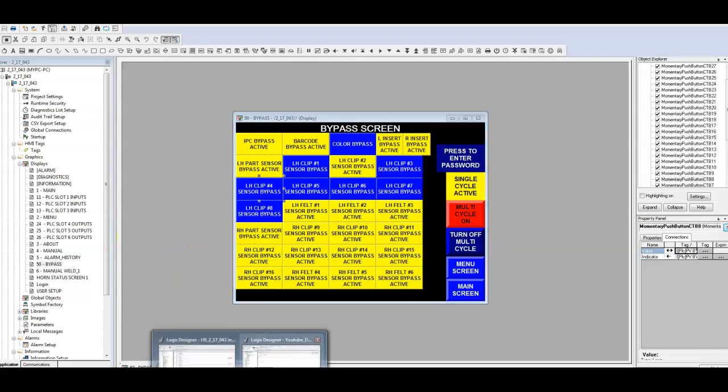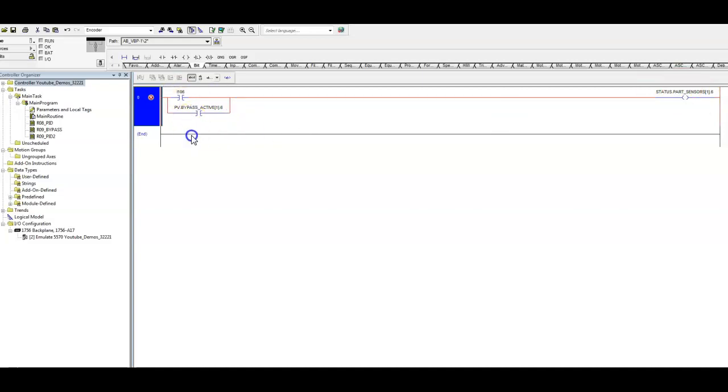So I'm sure when you're thinking about bypass, you're thinking right here, this is a typical sensor rung. So here's our input for our sensor. This is our output. In this case, this is a UDT, user-defined data type status bit. And right here, we have our bypass. So either one of these, an OR statement here. So either the sensor or the bypass will energize the status bit for the input. Very simple. However, I want you to look at a couple of other things as well before you just assume that that's all that you need to do in order to build a bypass in your PLC routine. So we're going to go ahead and get started. I'm going to share with you my thoughts of how you might want to build a bypass into your program.